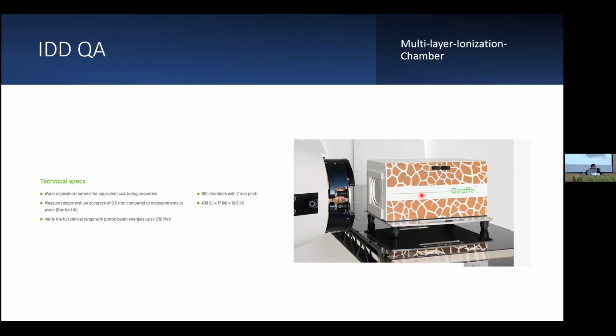So I checked spot shape and size to make sure something scatter-wise didn't change, and checked the depth doses, just a few of them to make sure something didn't change. And that aspect picked up, hey, there was something different. So this is the IBA, the giraffe. This one has a bunch of multi-layer ion chambers in here. You put a spot through there, and then you can measure that spot profile. It's not a true integrated depth dose because it's not in the water and it doesn't measure everything, but you could get a good measurement and quality assurance to make sure everything is acting right.